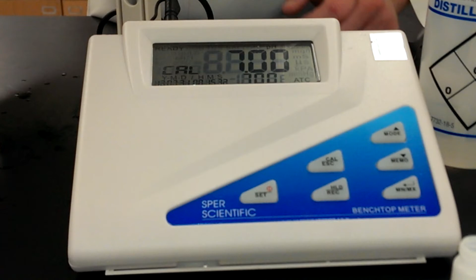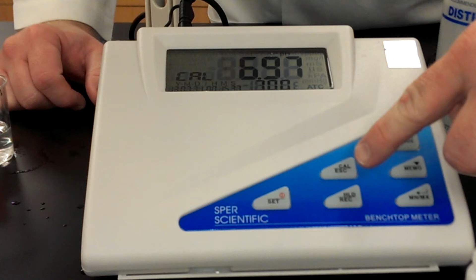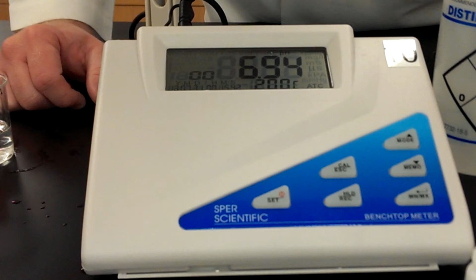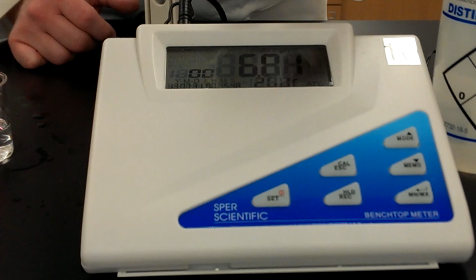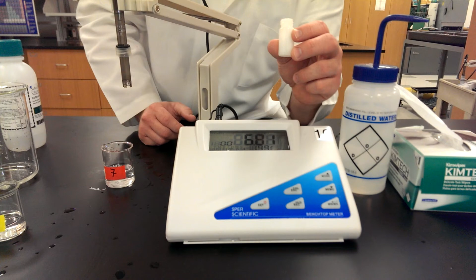Perfect. So once we've done that, you still have the cal flashing on the screen. Go ahead and clip this back on your arm if you've taken it off. And you're going to push the escape button, which is the same as the calibrate button. So you push that, and that's going to go back to your regular mode of measuring pH. Now, you can go ahead and use this after you've rinsed it with DI water and patted it dry. You can go ahead and use this to measure the pH of the solution you're using for your experiment. Or in my case, I'm going to be putting this away, so I'm going to store it.